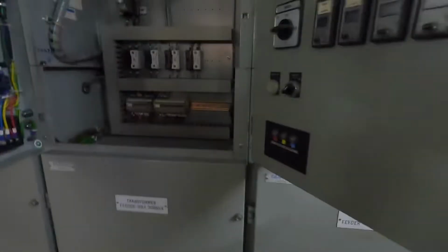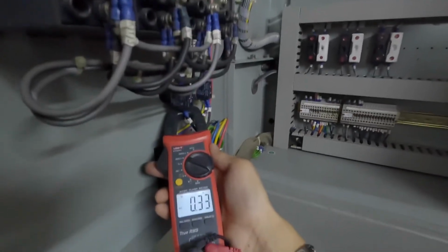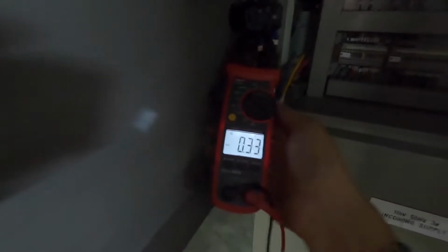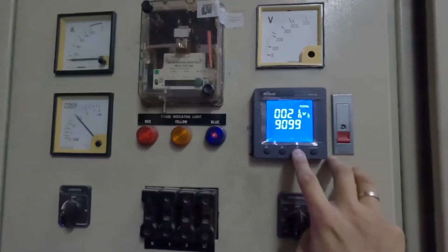Okay, here we have 0.16 amp. Okay. If there is amp, it means the heater is okay. Okay, here we have 0.3 amp. Alright. That heater uses only a little amp. 0.3. Same. 0.3. Okay, heater is in good condition. Okay, this is a chiller room. Okay, within permissible range. This voltage is important to maintain.